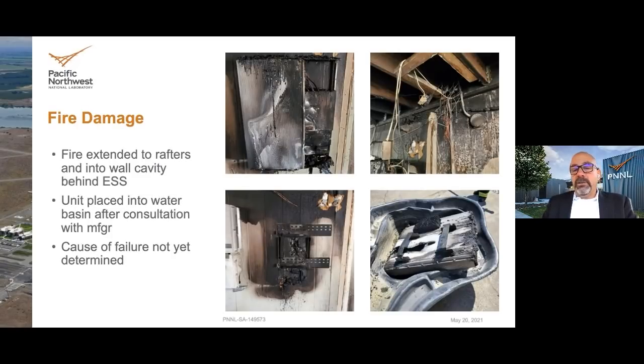For the responders on this conference, the best practice is to protect the exposure and apply water. It's very difficult to put out a cell that's gone into thermal runaway, and because of the casing, even directing a hose stream would have limited effect. So the recommendation is to protect the exposure. Again, this is an outdoor installation so ventilation is provided, but for indoor installations the explosion risk is significant.